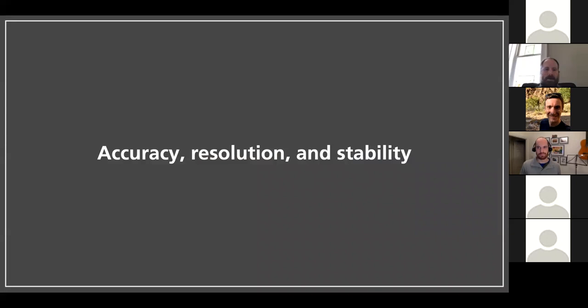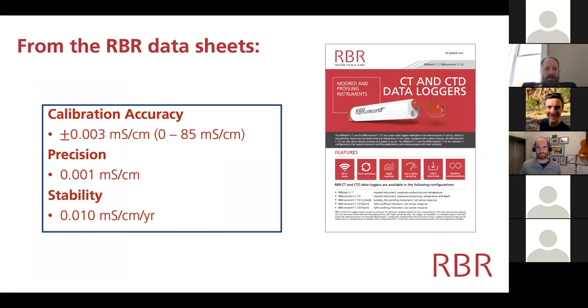When we talk about accuracy, and the second item should say resolution, and the third item is stability, our data sheets are clear. The range over which we calibrate the instruments is 0 to 85 millisiemens per centimeter. We can build instruments that go up to much higher conductivities, for instance, in brines or highly saline bodies of water. We've done instruments up to about 200 millisiemens per centimeter. But the accuracy on our standard instrument is plus or minus 3 microsiemens per centimeter, and that's a one standard deviation number. That's in line with WOCE recommendations, WOCE standards. The resolution, not the precision, but the resolution, is about 1 microsiemen per centimeter.